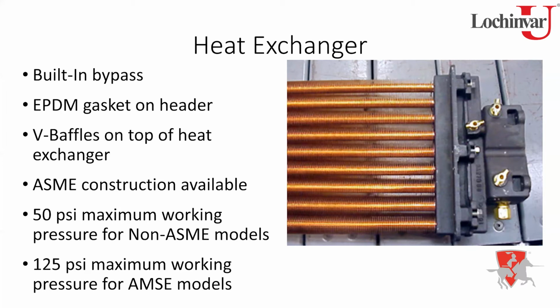You saw on the previous slide, we do have the V baffles on top of it. And like Charles said, that's to slow the flue gases down just enough to where we collect all the heat we can without slowing them down too much to where we start to condense inside of this cabinet, because this is a non-condensing unit. Those acidic flue gases could form into a condensate, and they can eat away at that copper. So if you ever get into this heat exchanger and you start to see a lot of green material or black material on this heat exchanger, that's a sign that this unit is condensing, and we need to figure out why. Is there something going on with the bypass?